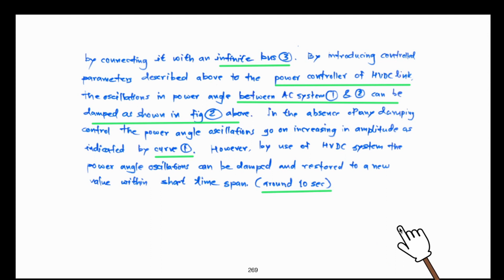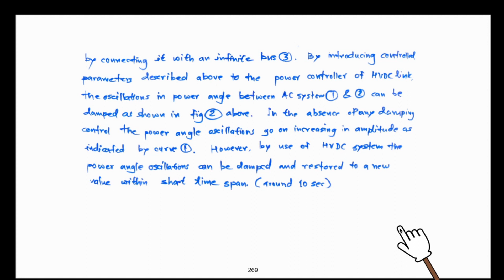So we have studied two types of parallel interconnection of EHVAC and HVDC network. One is a synchronous AC network, and the other one is an asynchronous interconnection. In asynchronous interconnection, the weaker AC network is connected to a strong AC system, an infinite bus, so the frequencies are different, that is why it is an asynchronous type. And damping is provided by providing an additional control parameter, that is the frequency deviation between the two networks, and so also tracking the changes in power angle with respect to time. So we'll stop here.